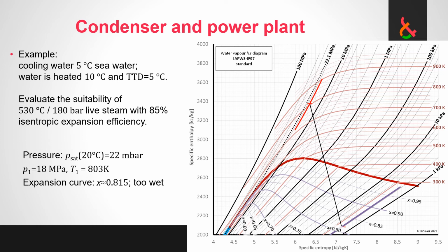It's going to be prohibitively expensive to try to increase it. Either you pay a lot of money for your superheaters, or you pay a lot of money replacing them very, very often. So what we do instead to move the endpoint of this curve to the right is move the start point to the right along the same temperature curve. So we reduce the pressure.